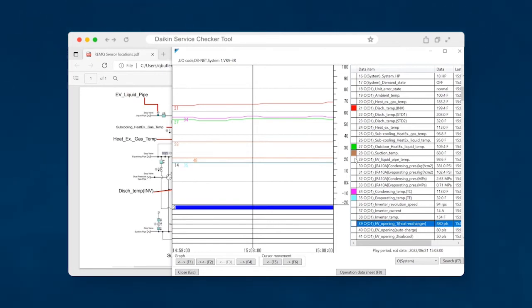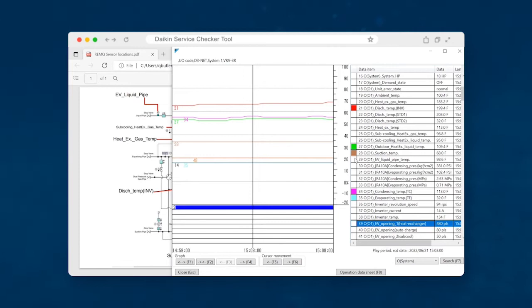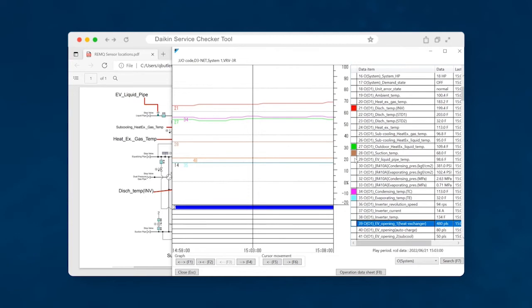Maybe let's say that you're on site now. And let's say that it's a cooler day. And now all of a sudden, the system is keeping up. Let's say that you get a call from your customer, and they say, hey, this thing wasn't keeping up over the weekend. And you go out and all the rooms are satisfied. And so you need a means to ramp the system up. So what you can do is go to your outdoor unit, and put the system into forced on mode. And it will drive all of the indoor units on, and then you'll be able to get a load on the system and get these benchmark numbers.